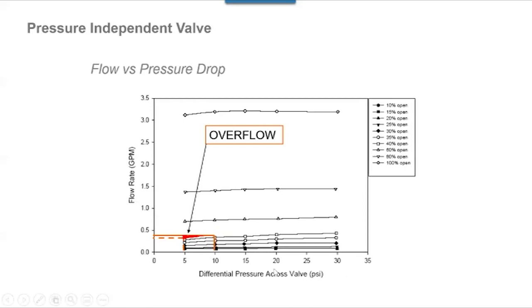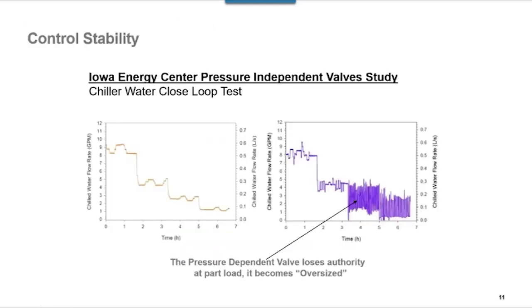The idea being is that if I have 5, 10, or up to 30 pounds or more across this pressure-independent valve, I don't want to see big swings in flow like we did with the globe valve in the previous slides. How does this translate more to the system? Well, continuing the test, they did a set point step test. And the idea of this was they started at a 56-degree set point and increased the set point every 4 to 5 degrees every 90 minutes. You can see by looking at this, the left-hand side is the pressure-independent valve. You look at the left-hand side, and those increases are pretty marked. You can see exactly where the increases were occurring. But look at the pressure-dependent valve on the right-hand side.